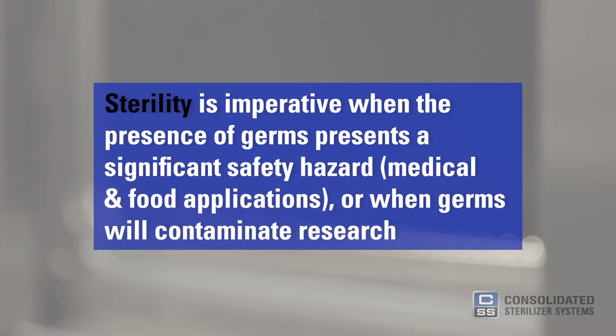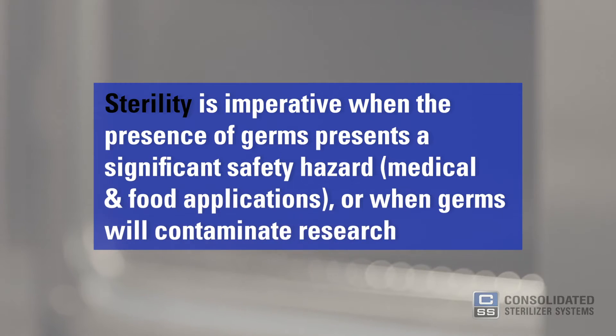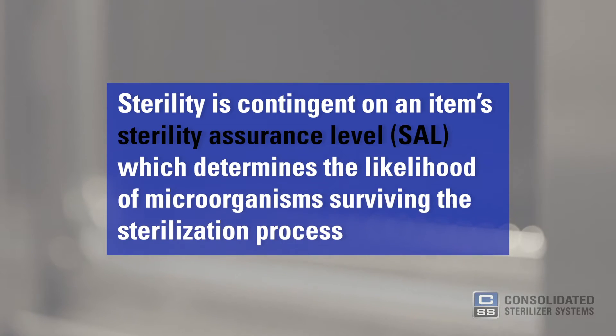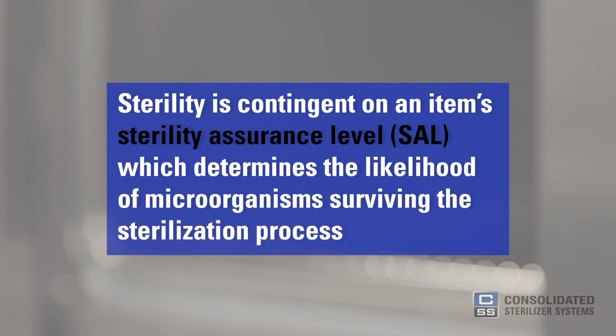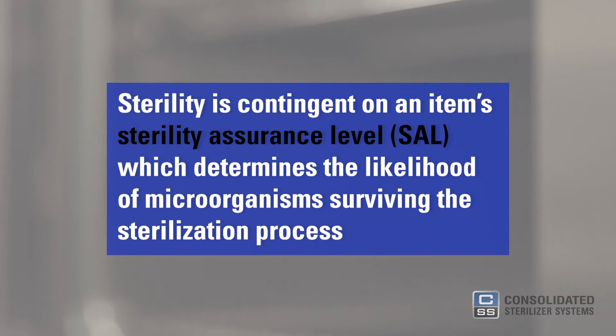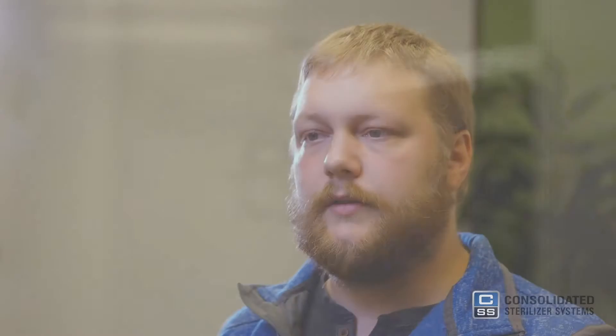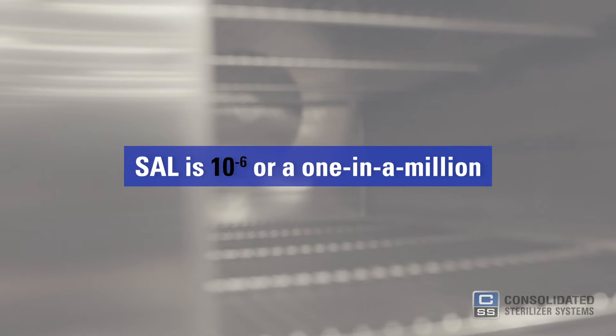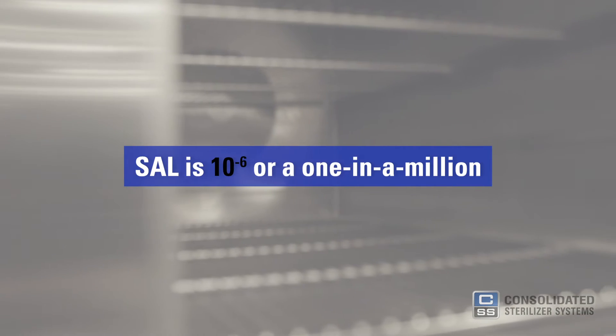Sterility is imperative in situations where the presence of germs would present a significant safety hazard — think hospitals, research laboratories, food production facilities, and so on. Sterility is contingent on an item's sterility assurance level, or SAL, which determines the likelihood of microorganisms surviving the sterilization process. The general standard for SAL is 10 to the negative 6, or a 1 in a million chance of a single viable microorganism surviving.